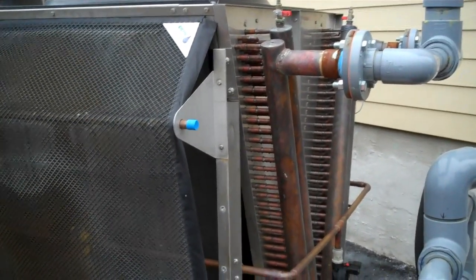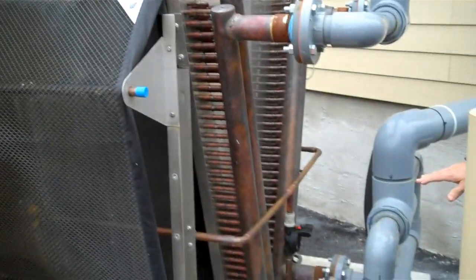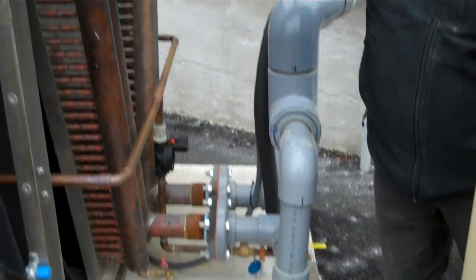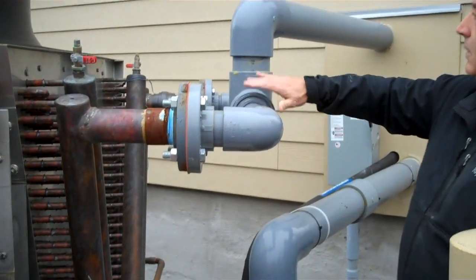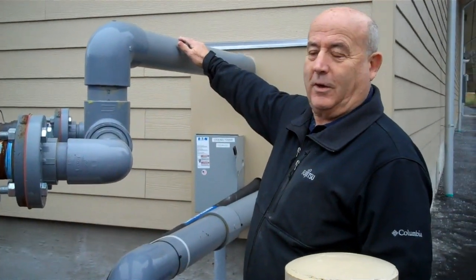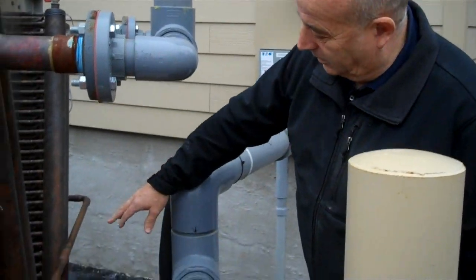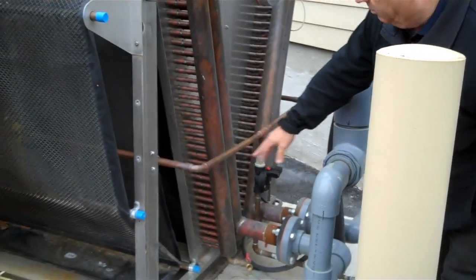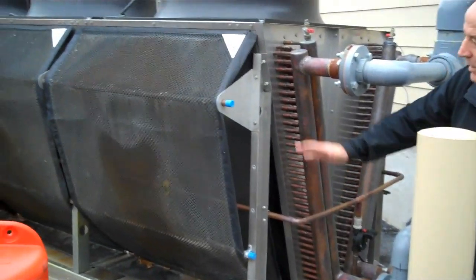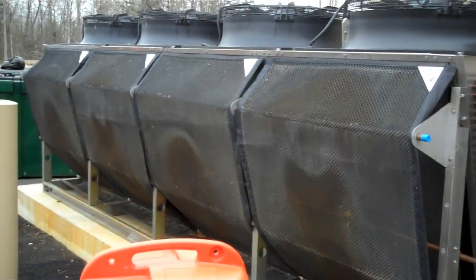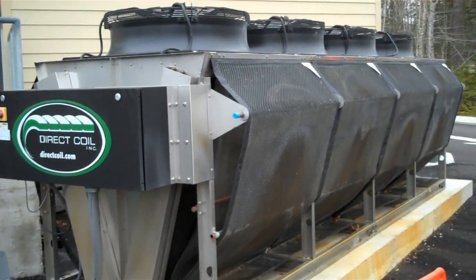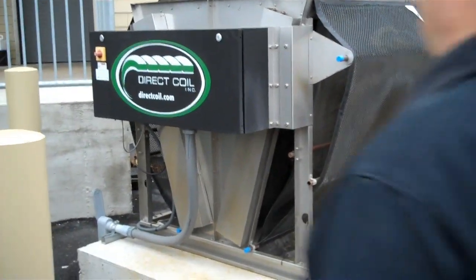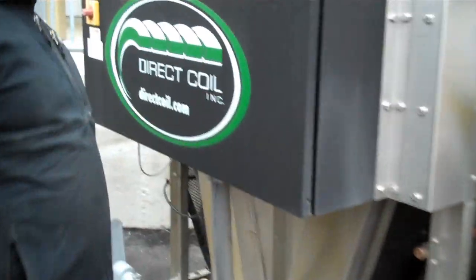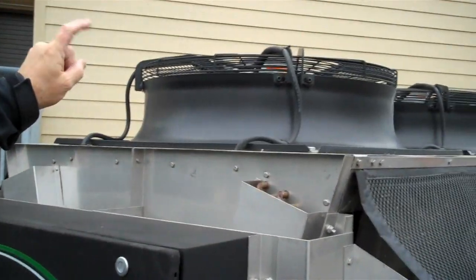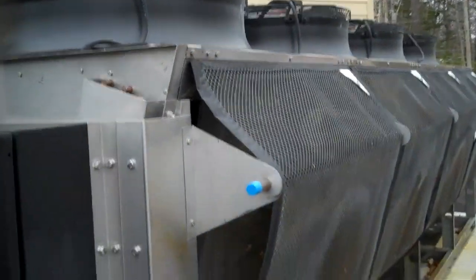This is where we dump heat when it's too warm. This is the fluid return, which goes in here to get cooled, and then this is the supply back to all the refrigeration and heat pump units. This is the water valve that our computer controls to spray the mist onto these adiabatic pads. This is an adiabatic cooler. Right on the very end here is the control panel. And these are all ECM motors that the controller controls.